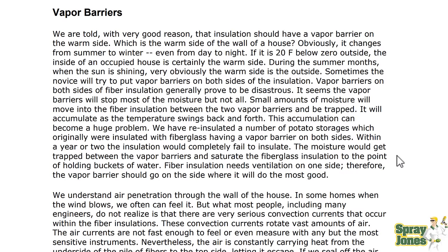We have re-insulated a number of potato storage buildings originally insulated with fiberglass having a poor vapor barrier on both sides. Within a year or two, the insulation completely failed. The moisture would get trapped between the vapor barriers and saturate the fiberglass to the point of holding buckets of water. Fibrous insulation needs ventilation on one side, so the vapor barrier should go on the side where it will do the most good.